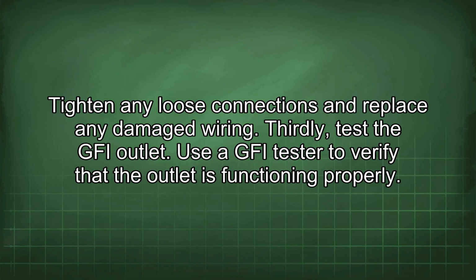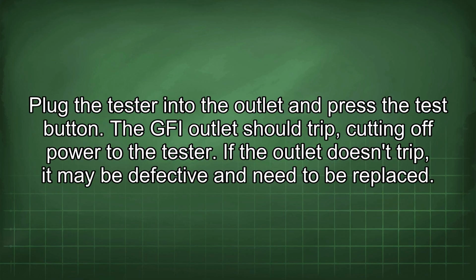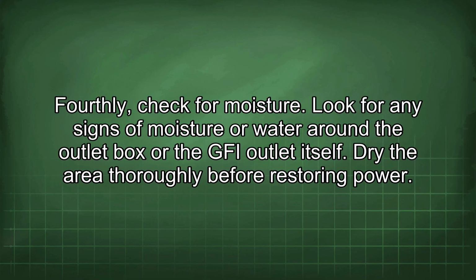Thirdly, test the GFI outlet. Use the GFI tester to verify that the outlet is functioning properly. Plug the tester into the outlet and press the test button. The GFI outlet should trip, cutting off power to the tester. If the outlet doesn't trip, it may be defective and need to be replaced. Fourthly, check for moisture. Look for any signs of moisture or water around the outlet box or the GFI outlet itself. Dry the area thoroughly before restoring power.